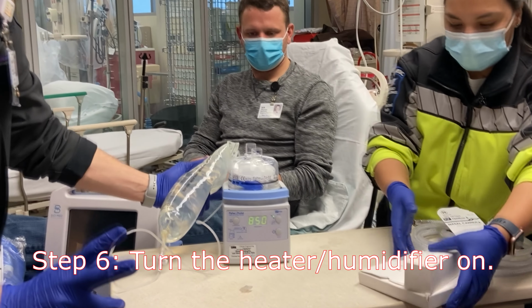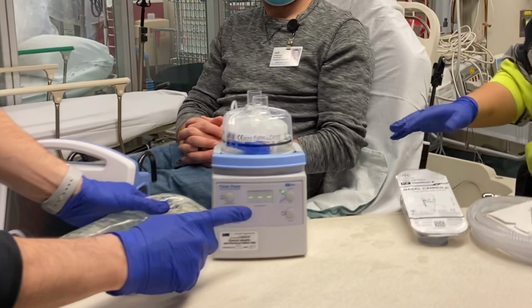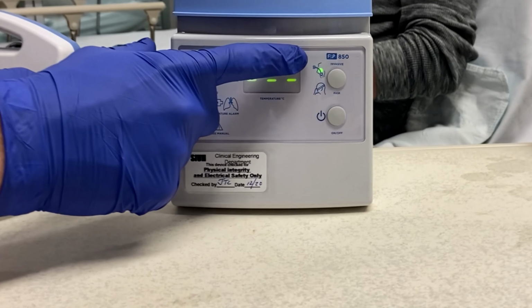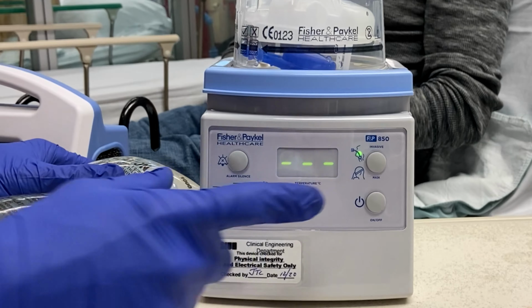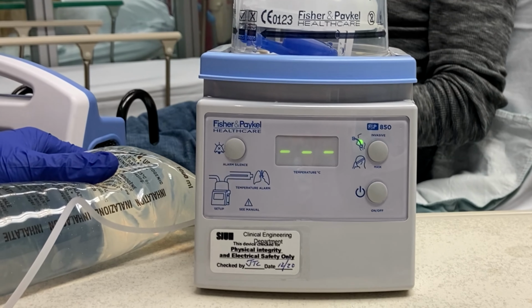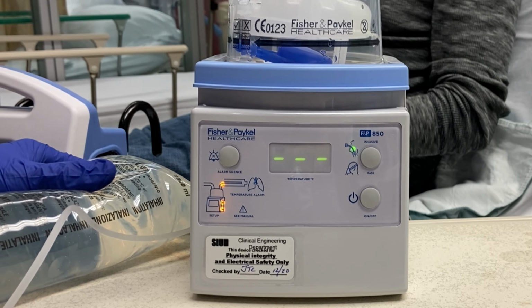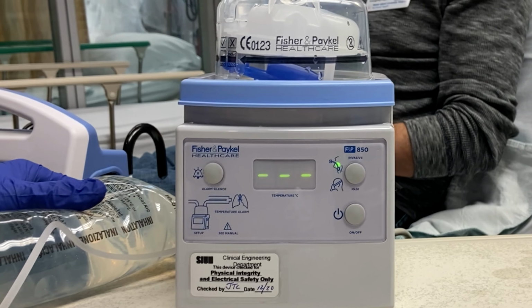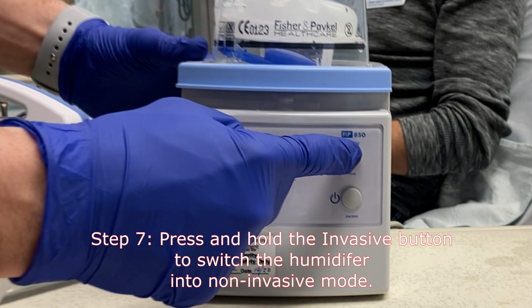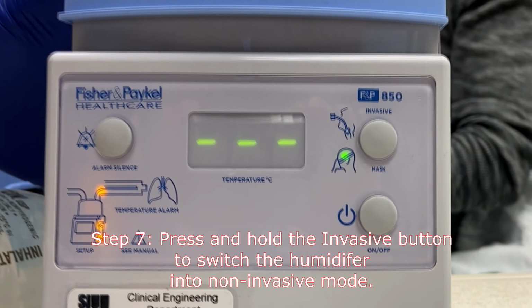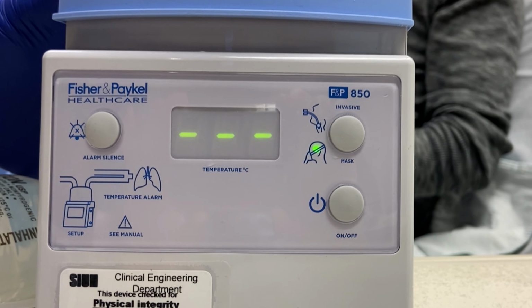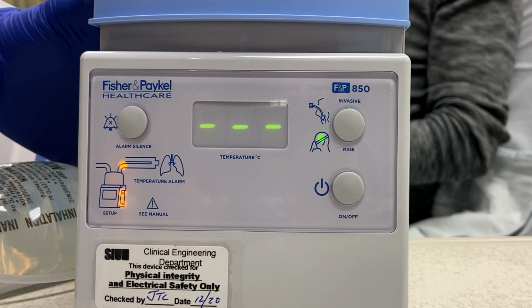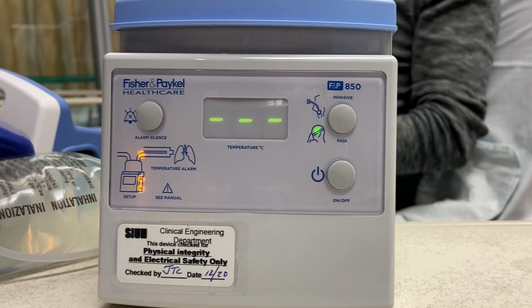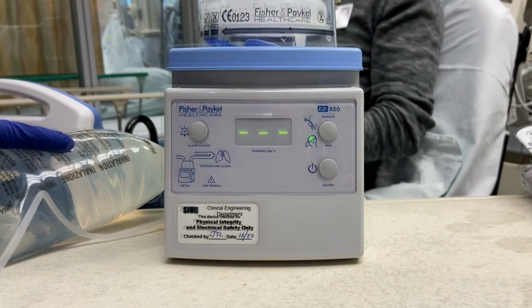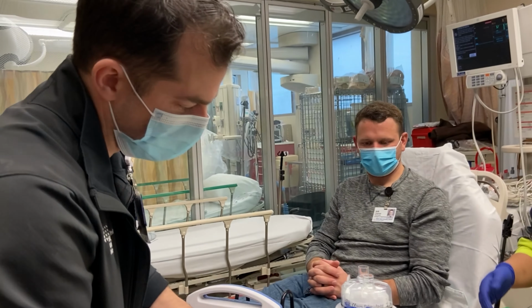there's two settings, for invasive or non-invasive. It appears to be preset at the invasive setting, which is a higher temperature than will be tolerated by a non-invasive patient. So we're going to press and hold the invasive button and have the green light identify that we're at a non-invasive setting, which is a temperature of about 30 to 34 degrees Celsius. The invasive setting is 37, which would be uncomfortable for the non-invasive patient to have.